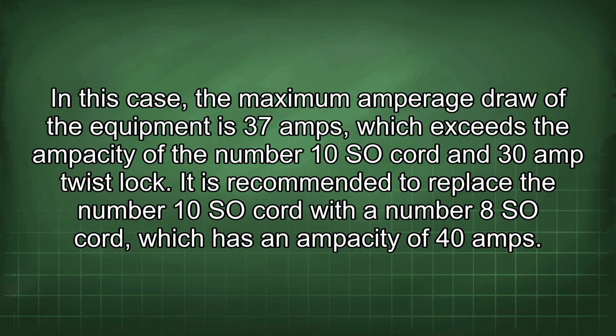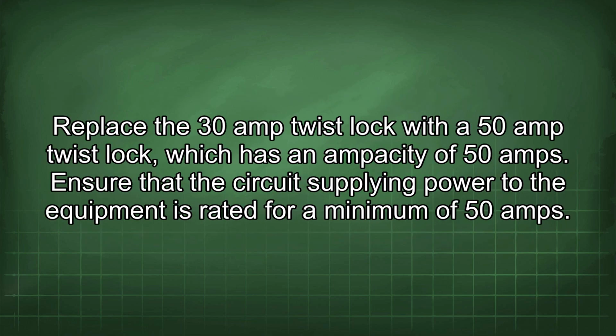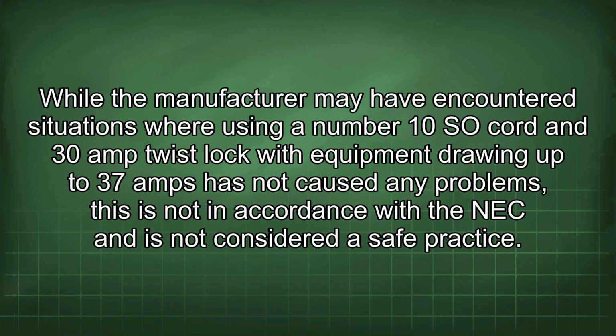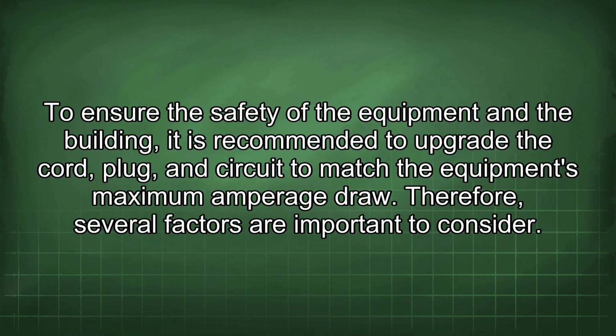It is recommended to replace the number 10 SOW cord with the number 8 SOW cord, which has an ampacity of 40 amps. Replace the 30 amp twist lock with a 50 amp twist lock, which has an ampacity of 50 amps. Ensure that the circuit supplying power to the equipment is rated for a minimum of 50 amps. While the manufacturer may have encountered situations where using a number 10 SOW cord and 30 amp twist lock with equipment drawing up to 37 amps has not caused any problems, this is not in accordance with the NEC and is not considered a safe practice. To ensure the safety of the equipment and the building, it is recommended to upgrade the cord, plug, and circuit to match the equipment's maximum amperage draw.